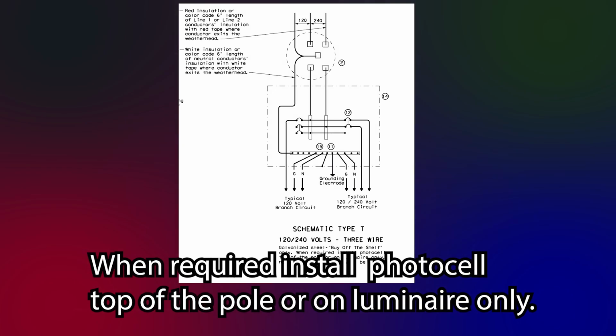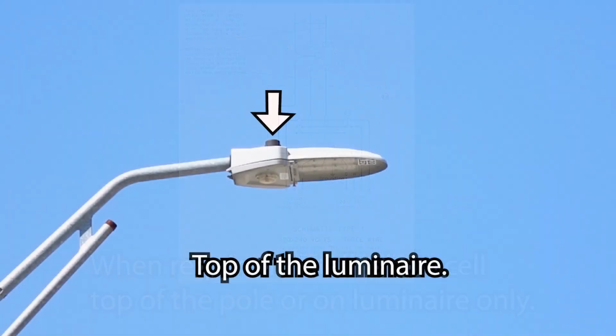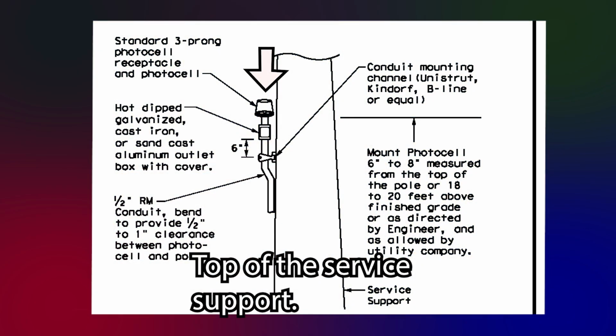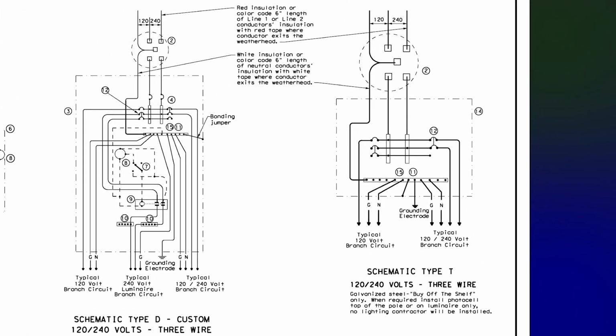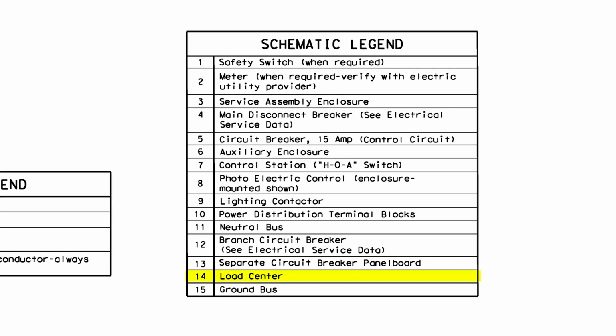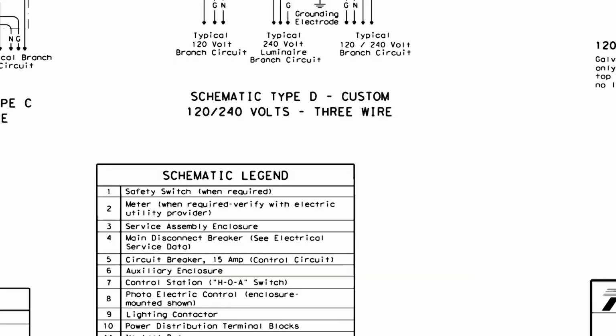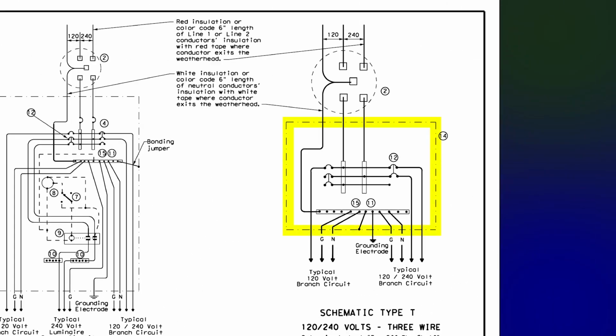signals. When safety lighting is to be controlled from a Type T enclosure, a pole-mounted or luminaire-mounted photocell can be added. Safety lighting that is powered from a Type T service will be controlled in one of 2 ways: a photocell physically located on top of each luminaire, or a photocell mounted at the top of the service support structure. On the diagram of a Type T electrical service on ED6, we see the service's load center is identified on the legend as number 14 in the diagram. This is outlined by the broken dashed line around the bus bar and branch circuit breakers.